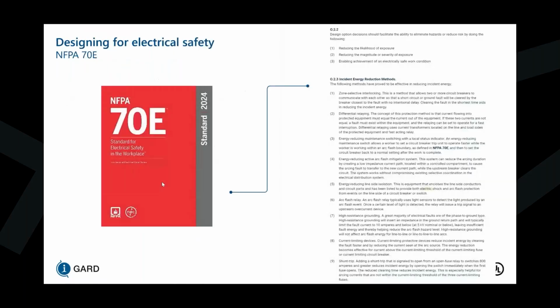Now in NFPA 70E, which is a standard for electrical safety in the workplace, we also have an equivalent in the Canadian standard, which is the CSA Z462. Both of them closely mirror each other. And in Annex O.2.2, it says that design option decisions should facilitate the ability to eliminate hazards or reduce risk by doing the following: reducing the likelihood of exposure, reducing the magnitude or severity of exposure, and enabling achievement of an electrically safe work condition. Further to this, in Annex O.2.3, they list out 9 different incident energy reduction methods.